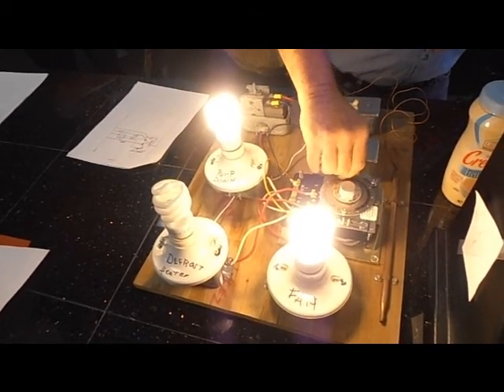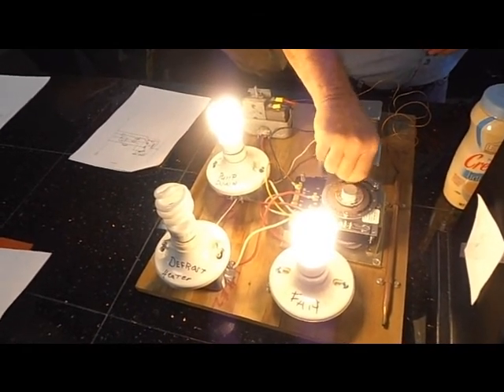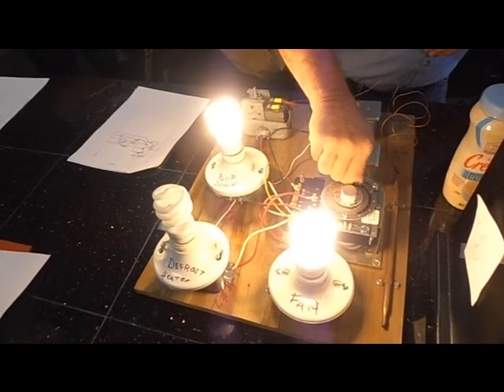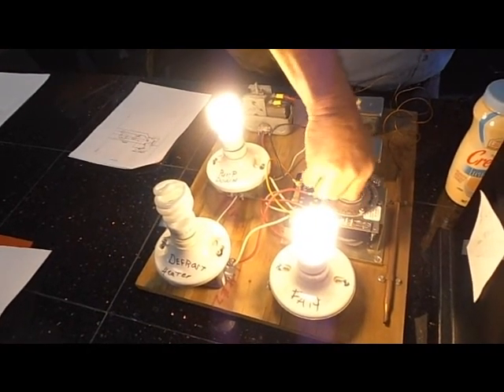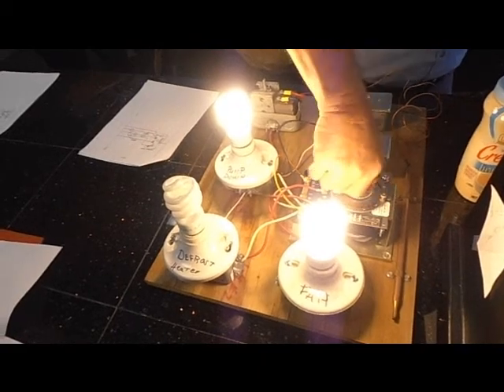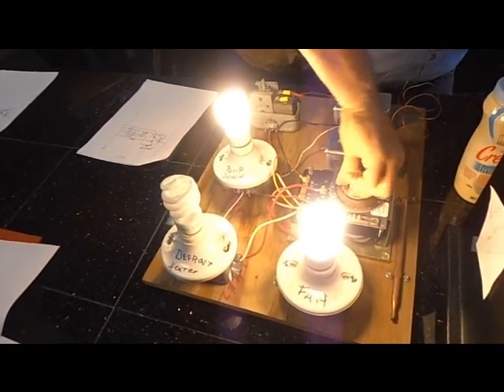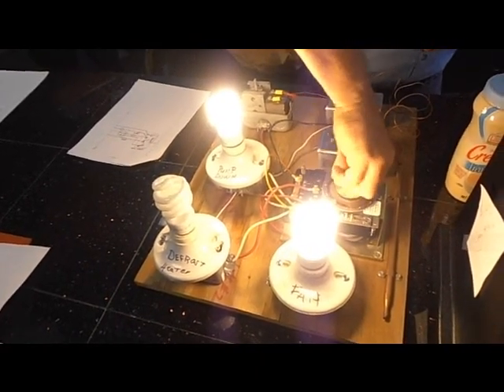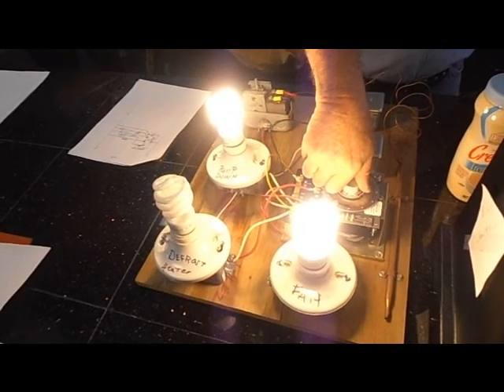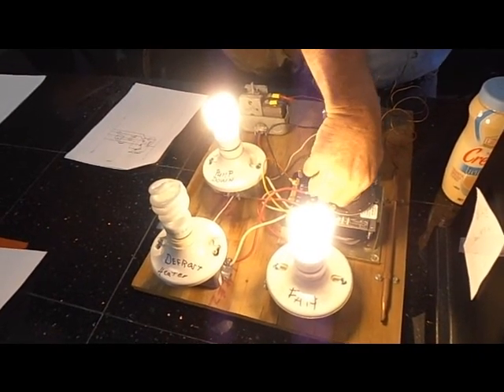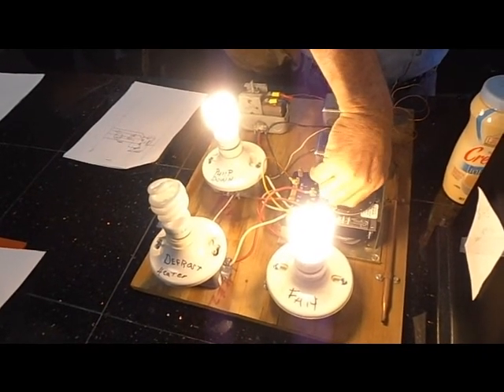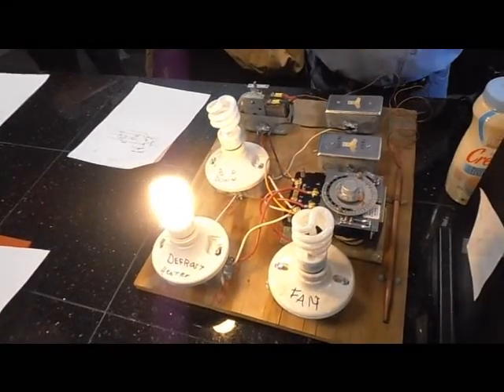As soon as I get the pin in there, and then once we get into a defrost mode, our liquid line solenoid cuts off, and our fans cut off, and then our heater comes on.